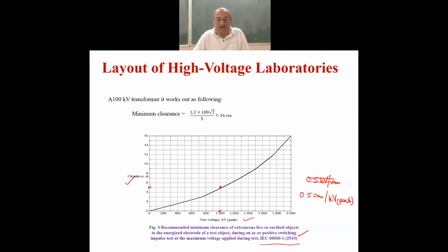Two of my colleagues, Hauschild and Lemke, have published a book. You can refer to it; it is there in the references also. They recommend the minimum clearance this way. For, say, a 100 kV power frequency transformer, the minimum clearance is 1.2 times the 100 kV peak value, that is 100 multiplied by root 2, divided by 5. Now that works out to be 34 centimeters. With the IEC estimation, it will work out to be 50 centimeters for 100 kV. So according to Hauschild and Lemke, the clearance requirement is lesser than that recommended by IEC.